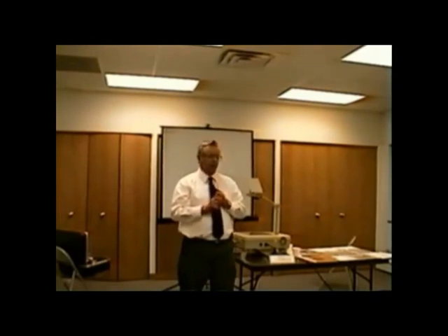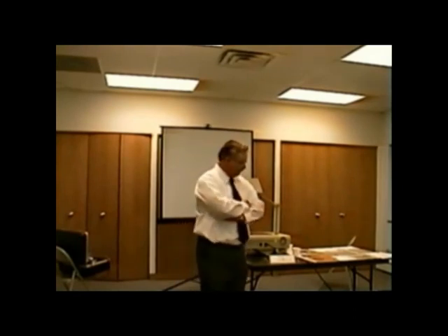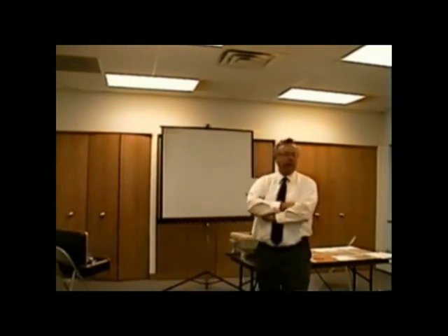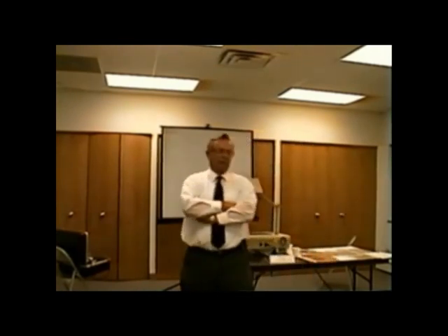You know, is it okay to leave in? Boy, I sure wouldn't. I'll tell you, that's getting very close to burning out. And that to me says that that furnace is going to go out at 2 o'clock in the morning and I'll get the call. At that point, the technician's got two choices.